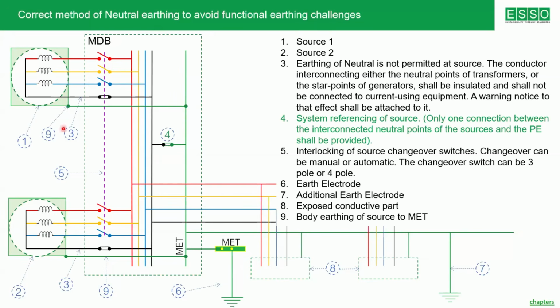That means the body of the DG or the transformer is directly connected to the earth bus bar of the main distribution board. You can see here this green color line, the body of the transformer or the DG directly to the earth bus bar of the main distribution board. Neutral of the respective source also directly to the bus bar of the main distribution board. Now the neutral and the earth are connected together. This is the system referencing, or this is the earthing. It is very easy to make and highly reliable.